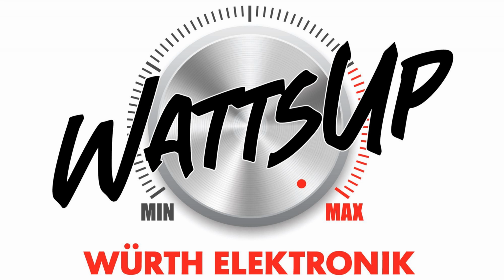In the average peak detector, the amplified intermediate frequency voltage is first rectified by a diode, which charges the storage capacitor to the current value of the envelope curve. The resistor is used for the later discharge of the capacitor. Afterwards, the voltage of the envelope curve is smoothed via the low pass from resistor and capacitor, so that finally the arithmetic mean, the average peak, is set at the capacitor. This display mode is selected because modulated carrier frequencies, as occur with switching regulators, can be displayed and assessed using it.